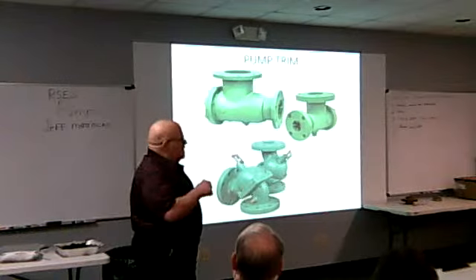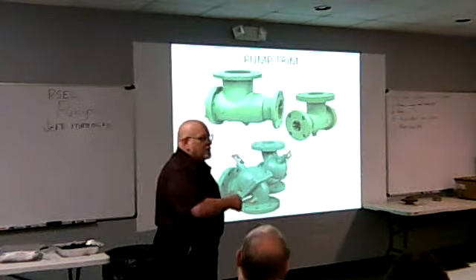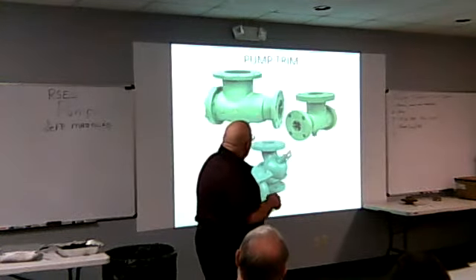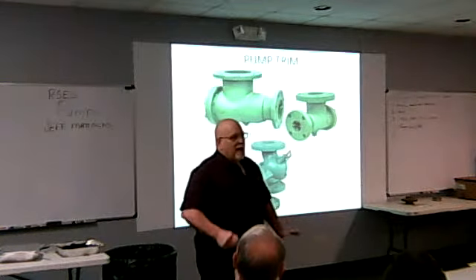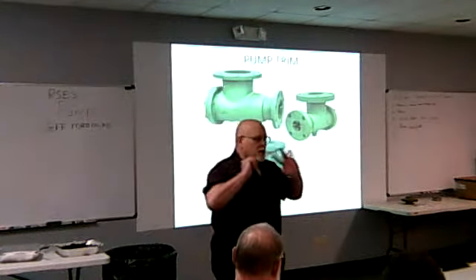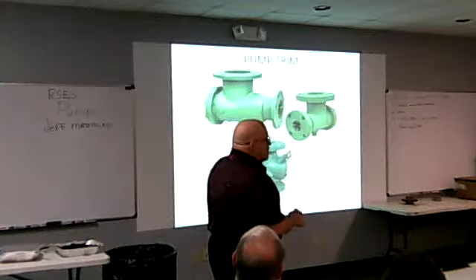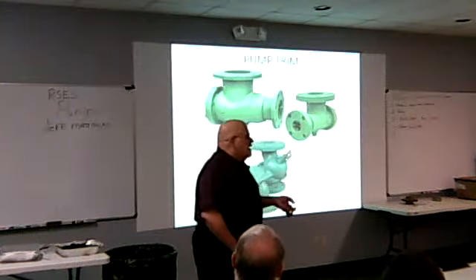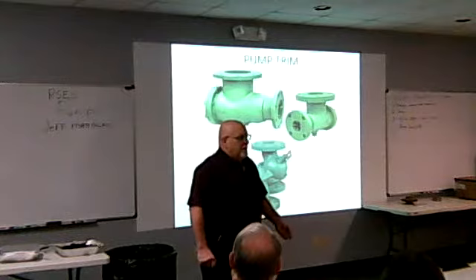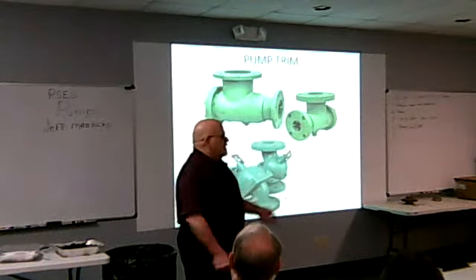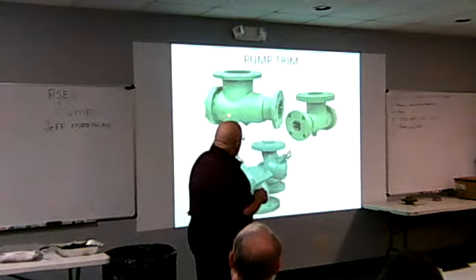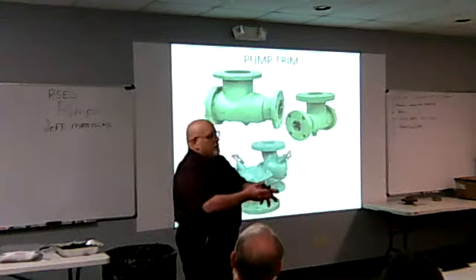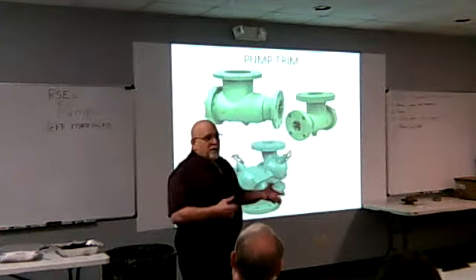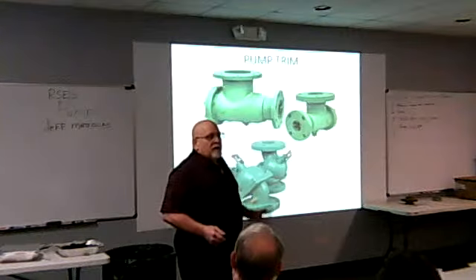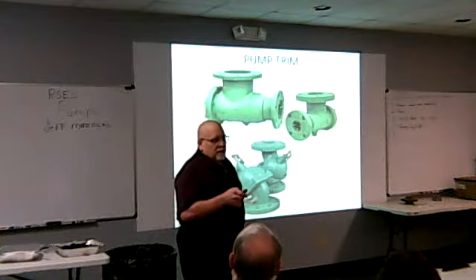Once these are started up, it's very important. After about a month or so, you want to go in and pull these. This is anybody's, not mine, Armstrong, Bell & Gossett, whoever. They all have this 20 mesh startup screen. It's a very fine screen. Over time, it will disintegrate. So once you get your system cleaned up on your original startup, you want to go in here, open this, pull that screen out and rip that 20 mesh off of there, and it slides right off. And then put it back together because you don't want it to disintegrate.